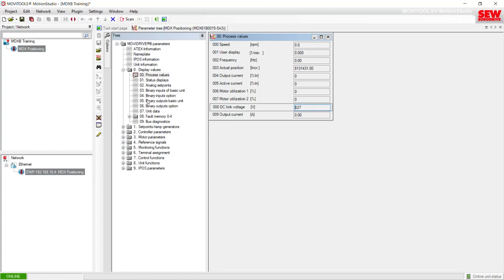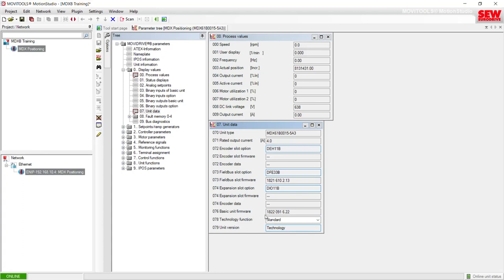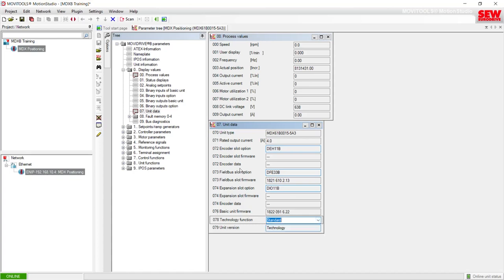There is one exception in item seven, Unit Data: parameter 78 for the technology function. Sometimes you may need to set this manually, but typically if you're using an IPOS program it will set this automatically and you would not need to set this manually. This is the only parameter in the entire folder group zero that can actually be changed — everything else is only for informational purposes. And parameter 78 would only be for special scenarios involving an IPOS program that needs this functionality turned on.